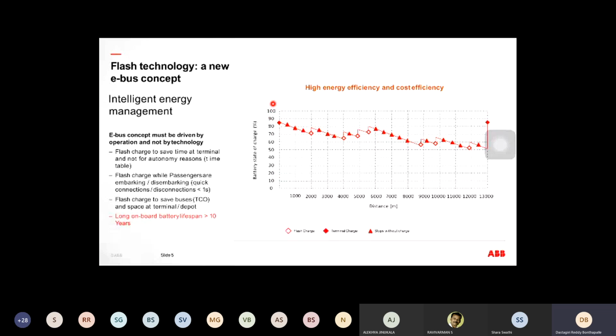The values I am saying, 85 to 100 and 0 to 20, may vary depending on chemistry, but the conclusion is that you have to slow down your charging in this area and at the top area, but in between you can charge it as fast as possible. Fast in the sense you can inject more current, you can utilize the C rate properly. So that's how we plan to use these two things. We limit the depth of discharge, and we don't go above 90 percent or below this percentage, where you have to slow down your charging.